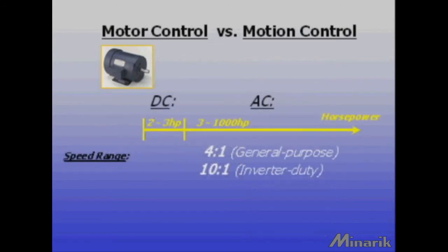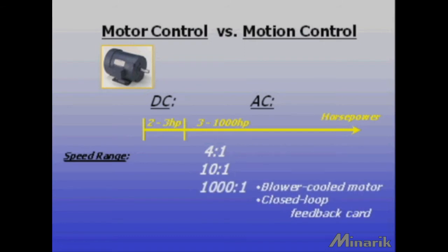AC systems often have cost advantages above 2 to 3 horsepower, but AC motors are typically limited to speed ranges of 4 to 1 for standard motors and 10 to 1 for inverter duty motors. Vector duty motors with external cooling can achieve up to 1000 to 1.